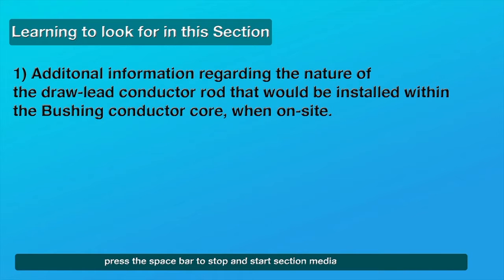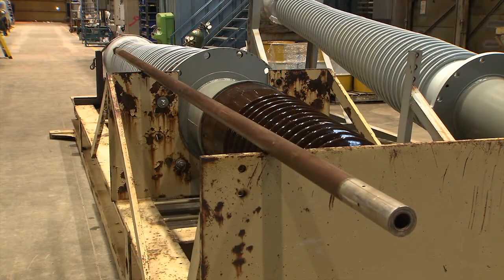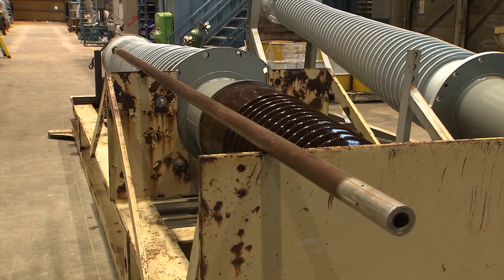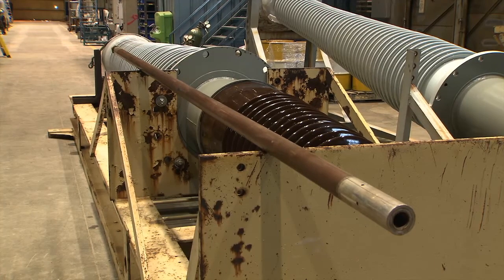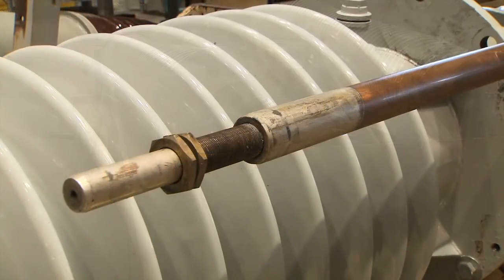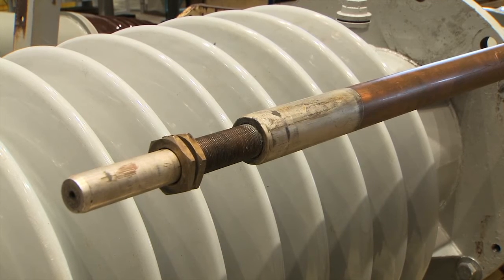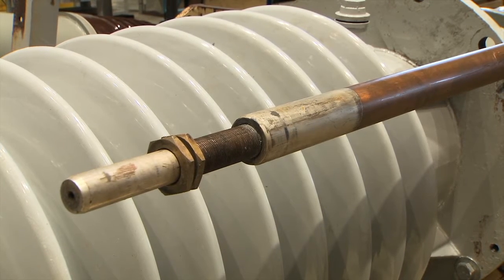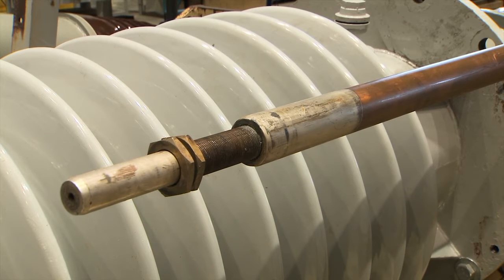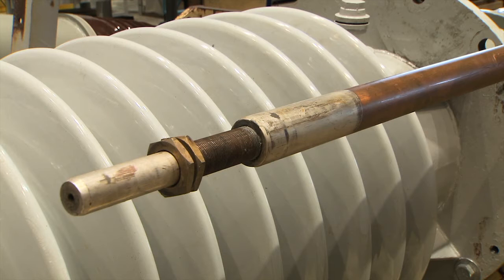Shots of copper draw lead conductor rods. When in service, a draw lead conductor rod like the one shown here is inside the conductor core of the bushing and carries the current from one end of the bushing to the other. In some cases, the draw lead conductor can be multiple pieces connected together. It's connected at the lower end to the transformer and at the upper end to a metal stud inside the terminal. When the bushing manufacturer supplies the draw lead conductor as part of the bushing, the current is limited to the rating specified on the bushing nameplate.